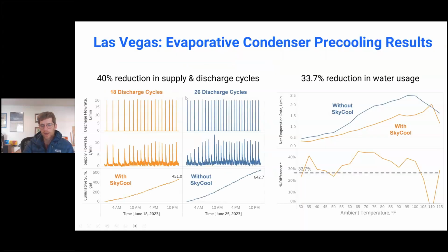But for this project, we installed flow meters on the water that went into the cooling tower, or the evaporative condenser, and leaving the cooling tower. So we could measure directly how many discharge cycles were on the tower, how much water was flowing into the tower to provide cooling. You can see for this plot on the left that there were a lot more discharge cycles when the array was off versus on, and that the water usage over a given day was reduced by about 30%. And then we correlated this data with the ambient over the course of a year. We're able to show nominally a 33% reduction in water usage when our system was on versus off.